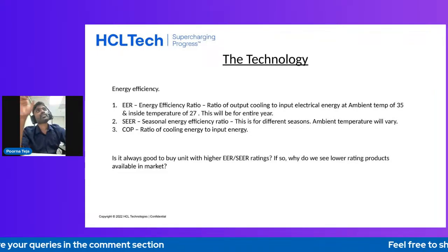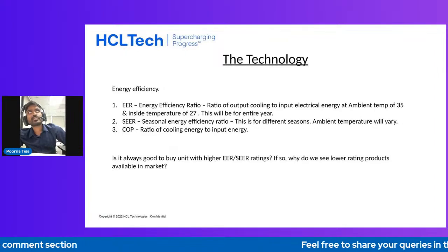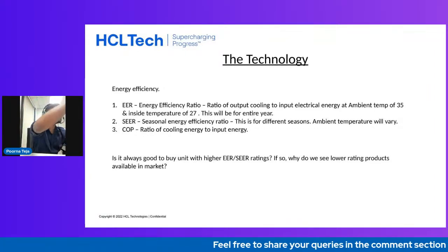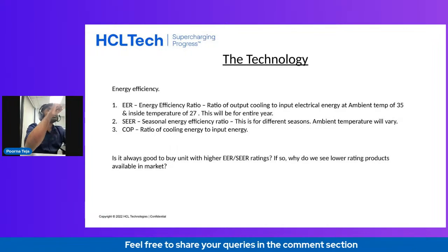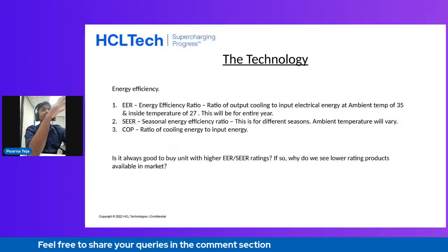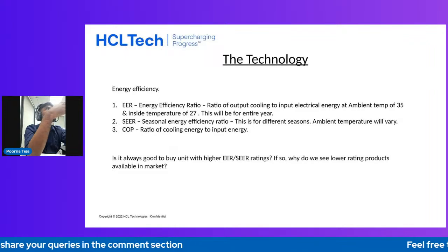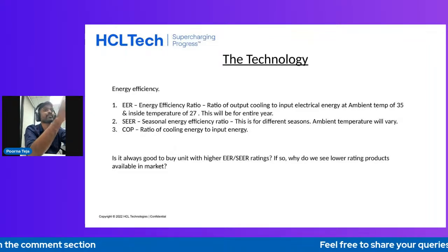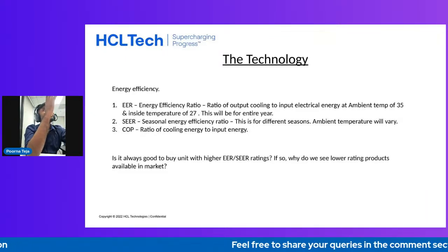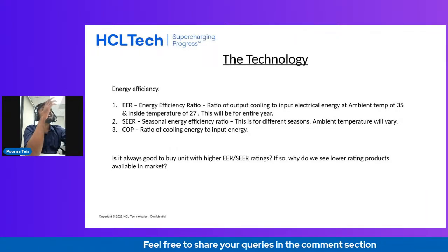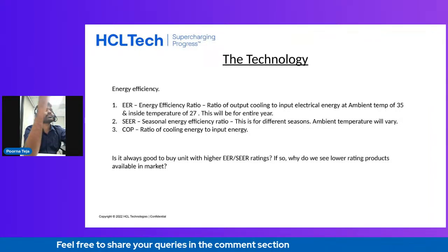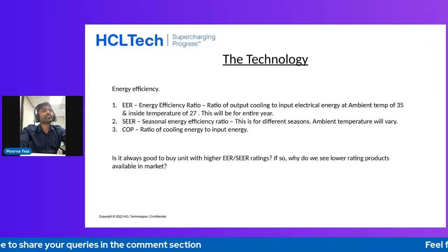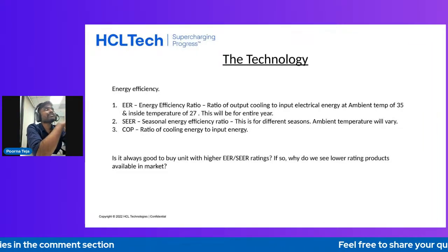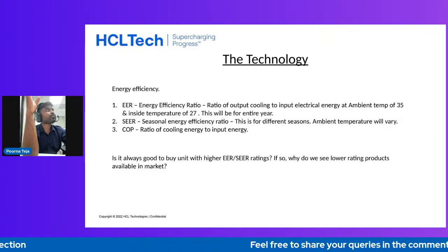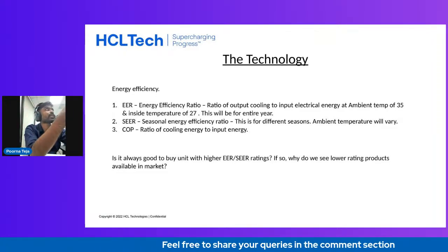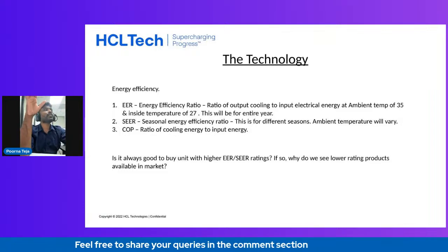If you have a 35-degree outside ambient temperature and 27 degrees inside the space you need to maintain, and you consider how much electrical energy you're utilizing to get this, only in that condition is the energy ratio valid. We calculate cooling output for the entire year and input energy for the entire year, and take the ratio.